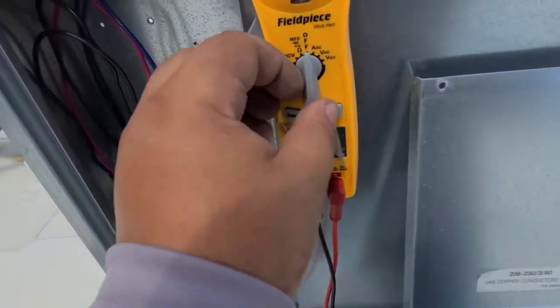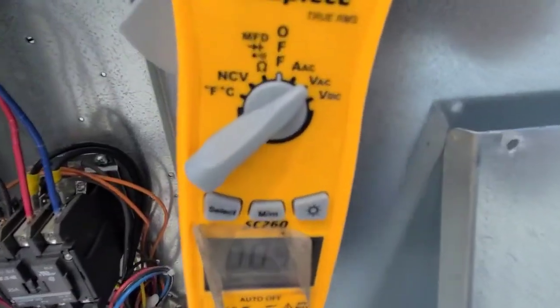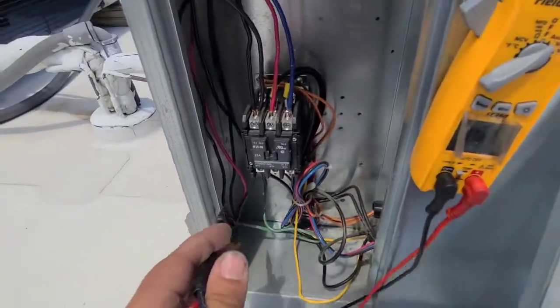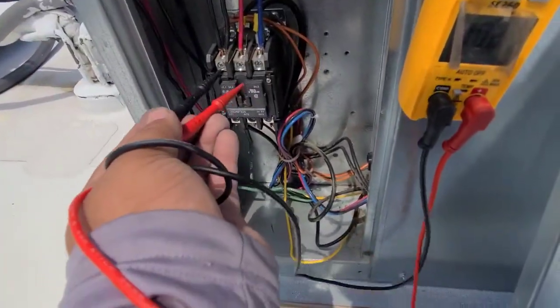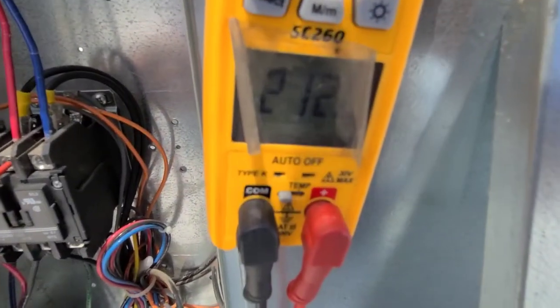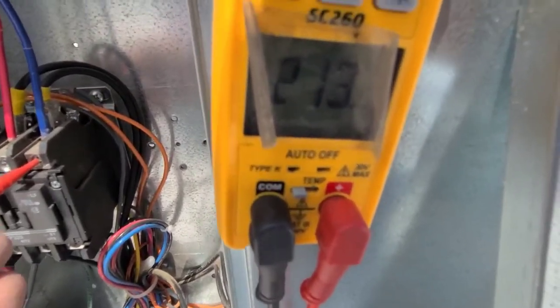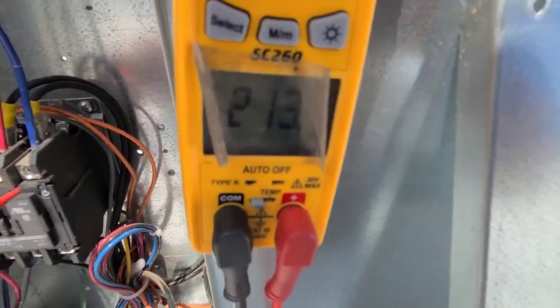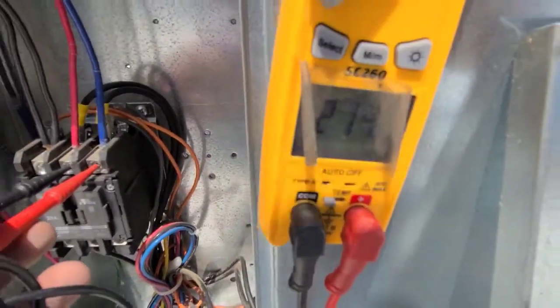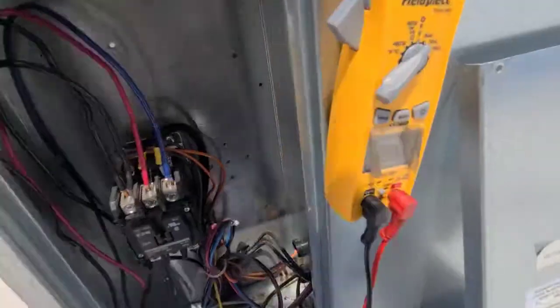Make sure we have the proper voltage going to it. Check that it's volts AC. Here's my power coming in on the top. I'm going to go from 1 to 2 — we got 212. 1 to 3 — 213. And 2 to 3 — 214. So that looks good.